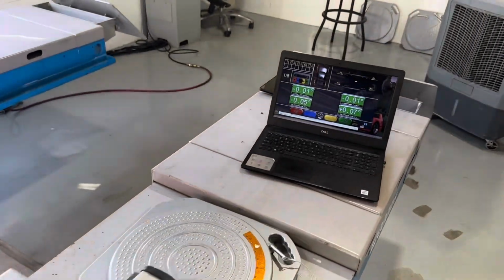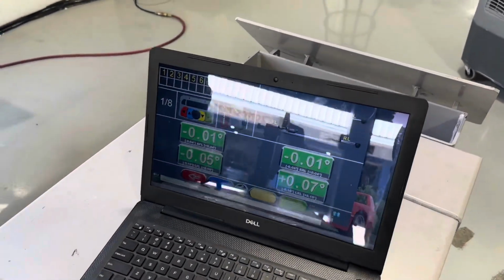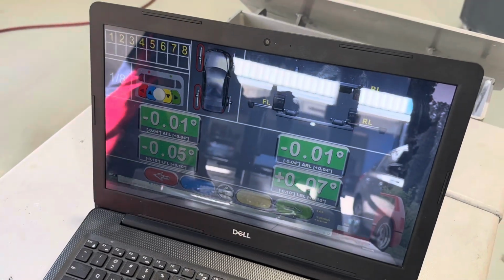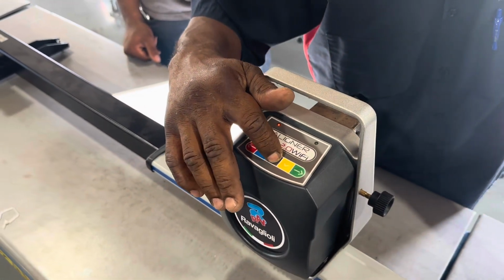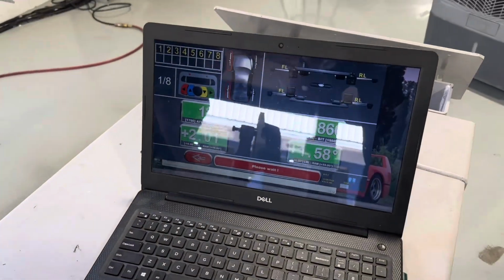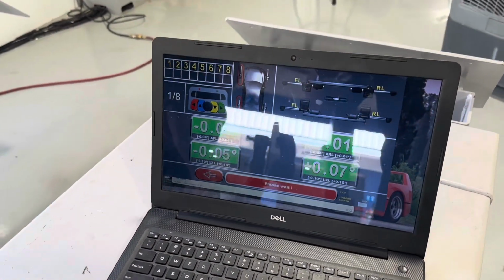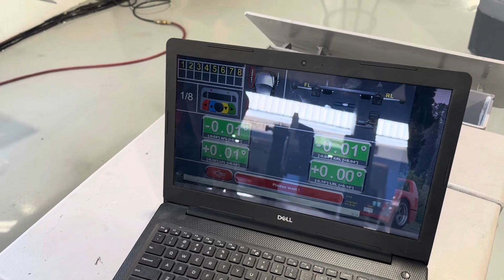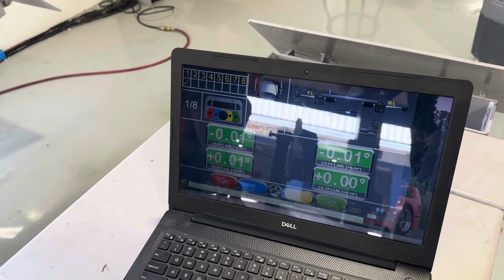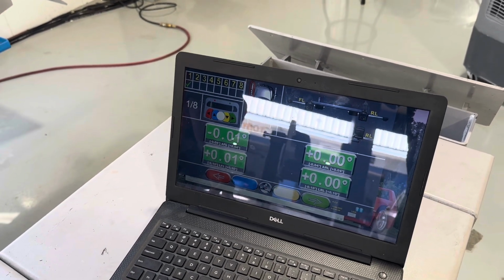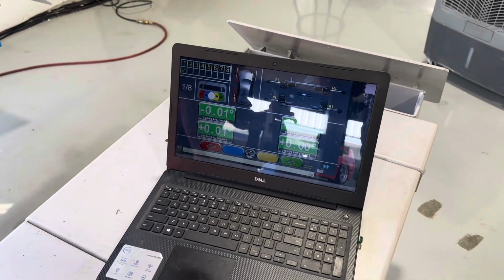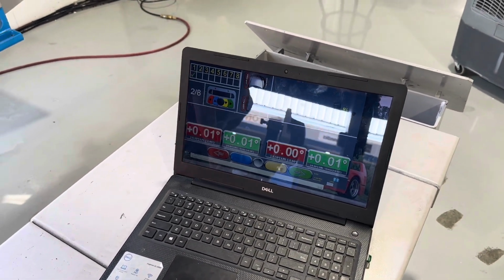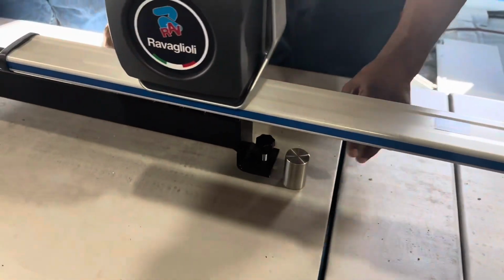Right, the machine needs to understand 2 things. It needs to understand 0 and it needs to understand 3 degrees. So we're now going to teach it 0 by pushing the grey button on the sensor. Right, it has now accepted that. So now we push the green button to go to our step 2 of 8 and we add the 3 degree spacer.